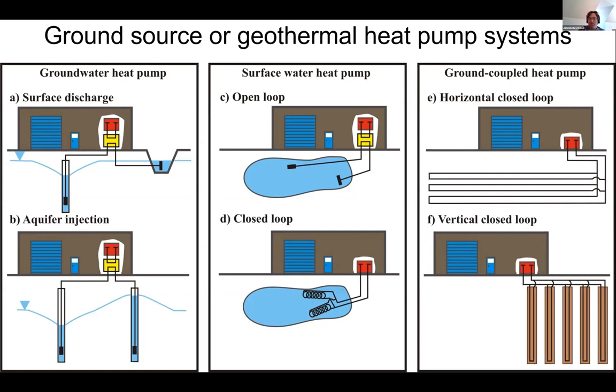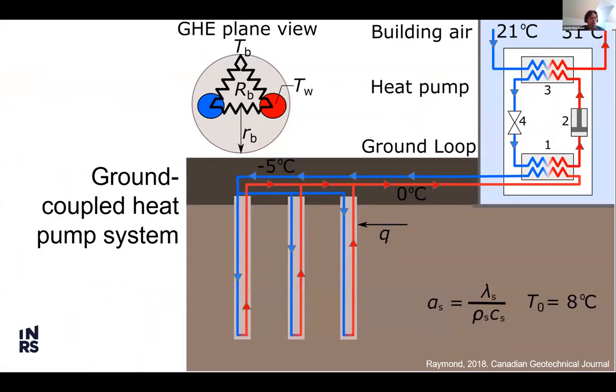In between, there are the surface water heat pumps, in which you take water from a lake or a pond to heat and cool the building, either in an open or closed loop fashion with some coil in the surface water body. But basically, in my talk, we'll discuss mostly the closed loop type, the vertical one, which is more popular for large buildings as well. The horizontal systems are quite popular for residential buildings, where you have a significant piece of land beside your building, and then you can install this type of system. In a downtown where space is limited, the vertical systems tend to be more installed, and they are the systems that need the most engineering and design to be operated in optimal conditions.